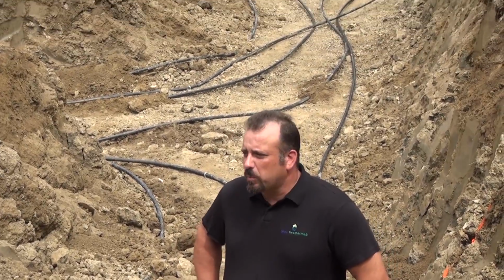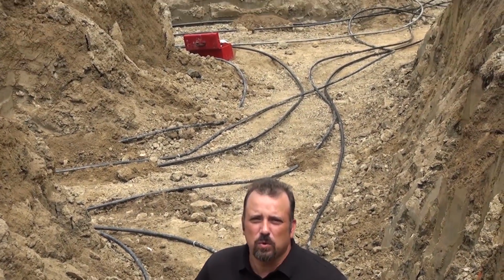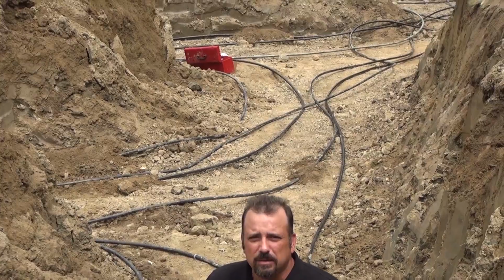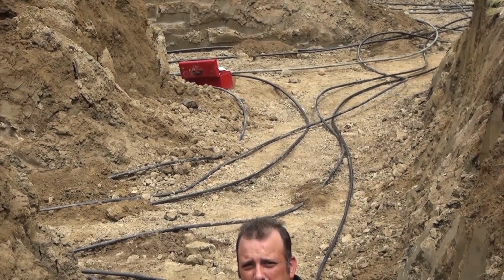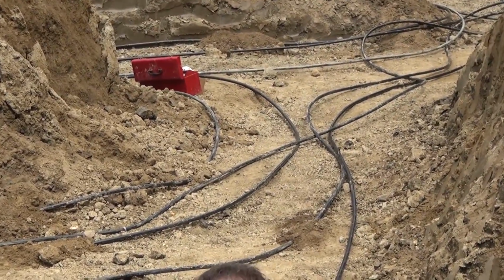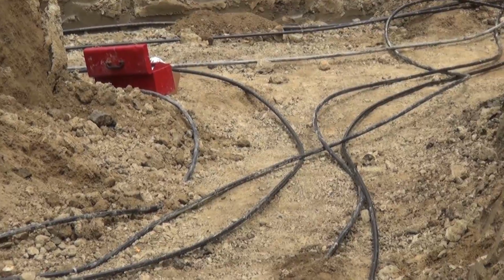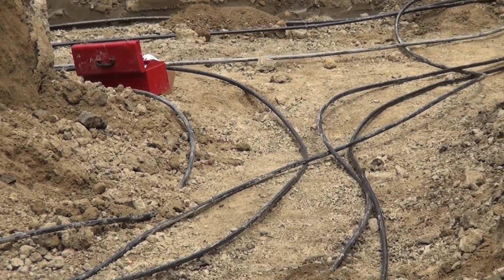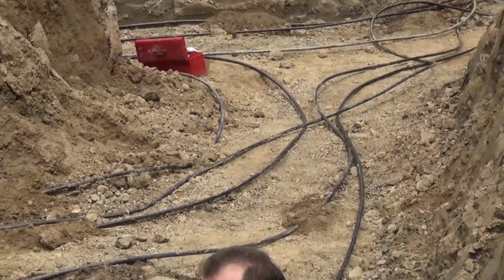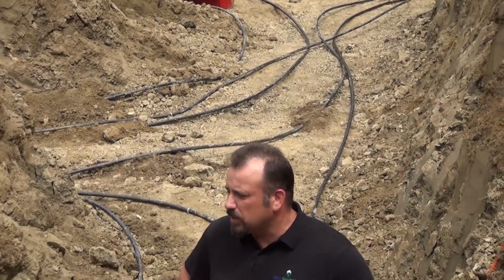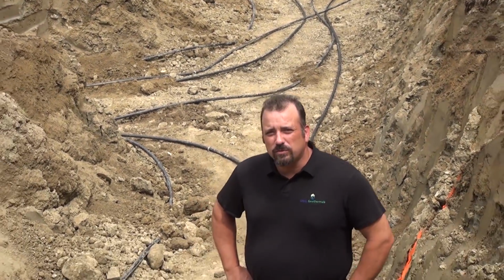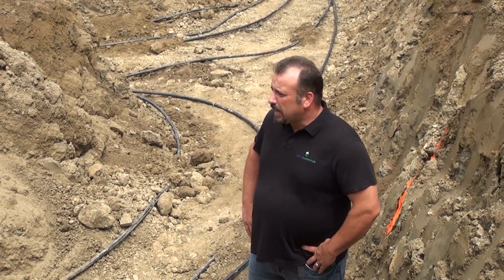Basically, a lot of folks want to understand how you take a cold fluid from the ground and bring it into a heat pump system and create heat, or release heat to the ground for cooling purposes. Well, this particular application is designed for a low loop temperature of about 32 degrees Fahrenheit. So the question is, how do I take a 32 degree loop temperature fluid, bring it into a heat pump, and make 95 degree air coming out of my vents in my house?